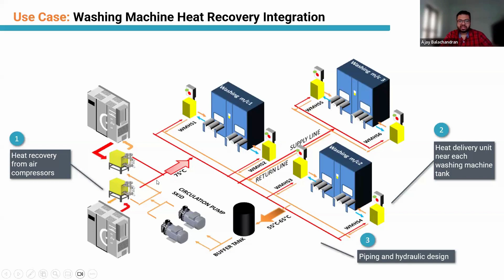So we audited the facility and found that they had multiple air compressors with them. We installed a couple of heat recovery systems and recovered the waste heat from the air compressors, and also designed the entire piping circuit as well as a heat delivery unit, so that all the recovered waste heat could be efficiently delivered to all the washing machines.